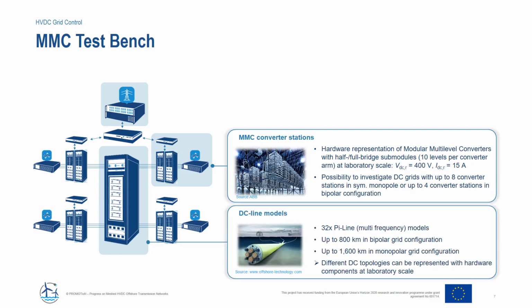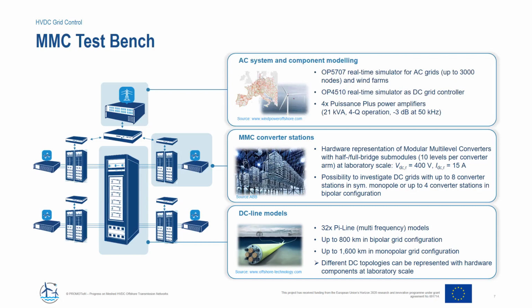The DC lines are represented using cascaded pi sections, and these are designed in a way to reflect a wide frequency spectrum. In total, we have 32 pi sections, and these are able to represent 800 kilometers of a bipolar grid or up to 1,600 kilometers of a monopolar grid. To integrate the test bench into the context of AC transmission systems and offshore collector grids, the MMCs are connected to a real-time simulator using linear 4-quadrant power amplifiers in a power hardware in the loop configuration. And this allows us to investigate and demonstrate the overall defined test cases within a laboratory scale.